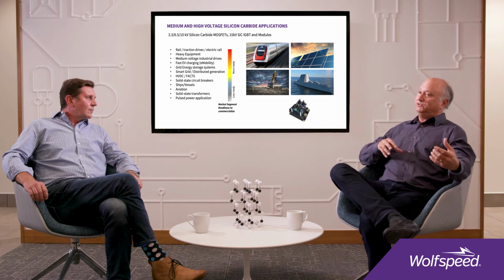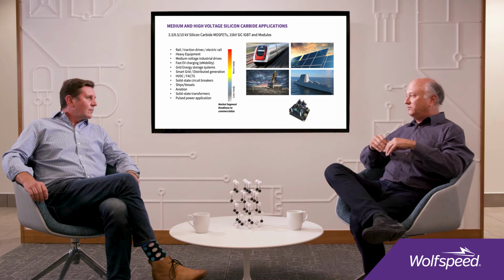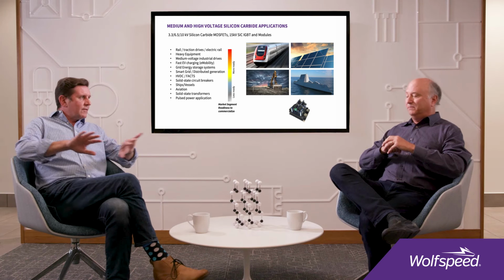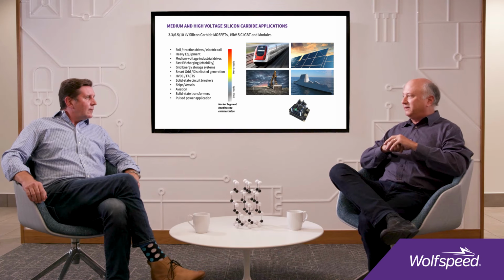And that allows you to look at things like solid state transformers, as opposed to using a big, huge 60 hertz heavy transformer that's lead and oil. We were able to use a very small one. Solid state transformers, or transformerless systems, is a bit of a misnomer because you still have to have a small high frequency transformer to isolate, for safety reasons. But it's the size of a bread box as opposed to the size of a car.